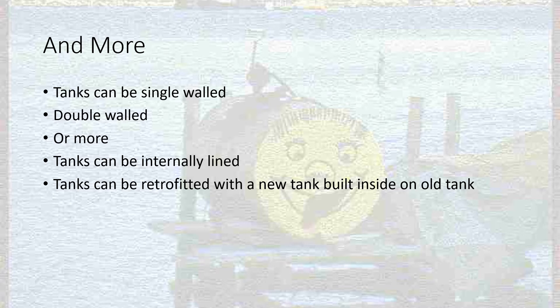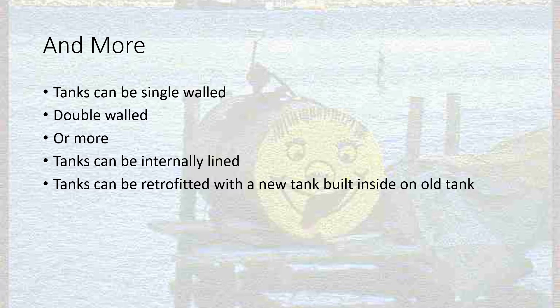Tanks can be single-walled — just one wall. With the new federal regulations that came into effect in 2015, they have to be double-walled. Some states, like California and Texas, already required double-walled tanks through state regulations prior to 2015. There are also triple-walled tanks — some hazardous substance storage locations require triple walls to help ensure no leaks. The number of walls is really only limited by your imagination; tanks can have four, five, or six walls.